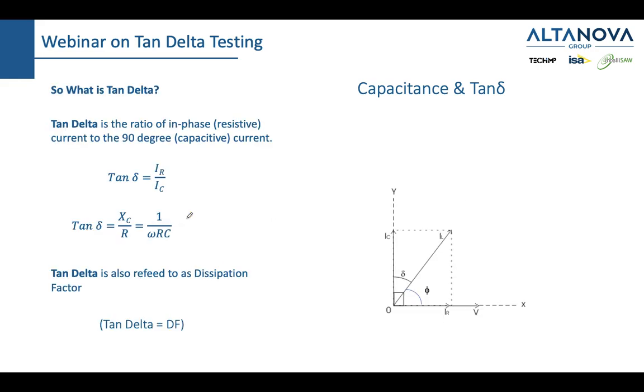So let us finally define what a tan delta is. Tan delta is the ratio of in-phase or resistive current to 90 degree or capacitive current. And we can see tan delta is IR over IC. If we play a little bit with the formula here, we can also see that tan delta is the reciprocal value of omega RC. Omega is a constant number. If we are doing a test in a European country, this would be 314. And if we do that test where the nominal frequency is 60, it's slightly higher. But anyway, you can see that the resistance and the capacitance with which we model the insulation are needed to calculate tan delta.